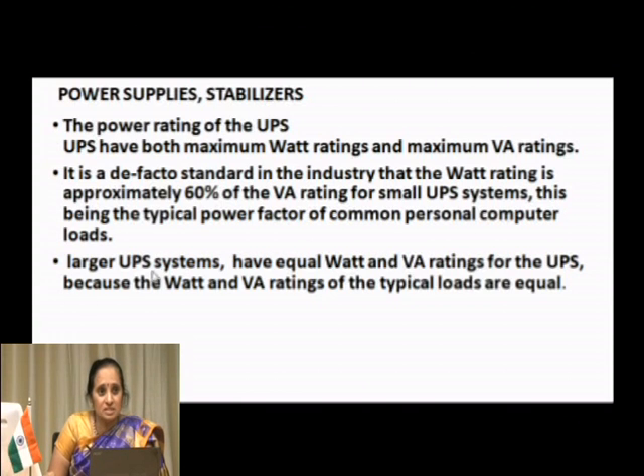In larger UPS systems, this problem is avoided because they have equal watt and VA ratings for the UPS, and because the watt and VA ratings of the loads connected are also equal. For large UPS systems with huge kVA ratings, this is the normal standard used. So in houses or in the IT sector where I use UPS for smaller loads, I have to take into consideration that the useful watt output is 60% of the VA rating, the voltage ampere apparent power rating.